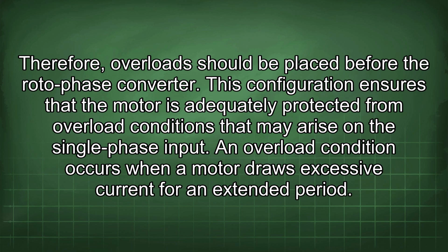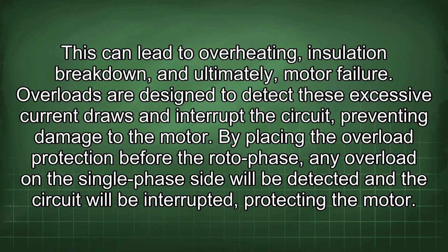An overload condition occurs when a motor draws excessive current for an extended period. This can lead to overheating, insulation breakdown, and ultimately, motor failure. Overloads are designed to detect these excessive current draws and interrupt the circuit, preventing damage to the motor. By placing the overload protection before the roto-phase, any overload on the single-phase side will be detected and the circuit will be interrupted, protecting the motor.